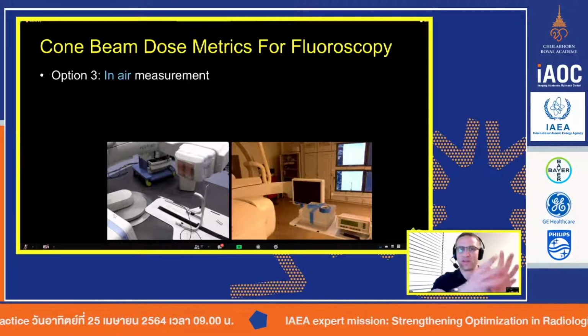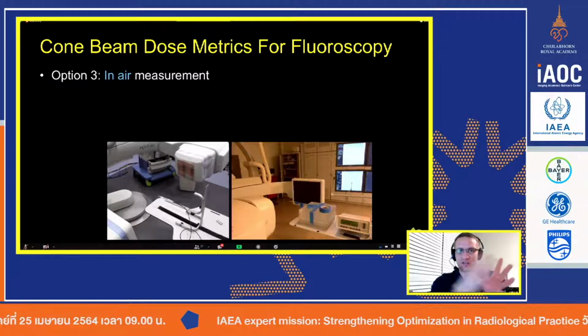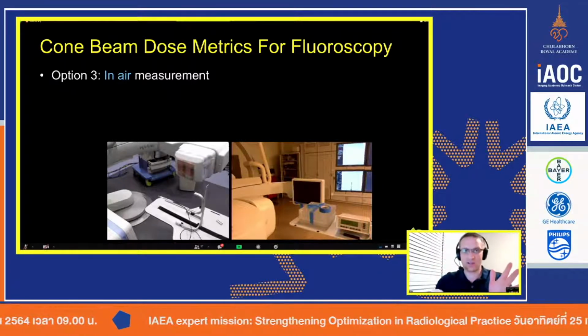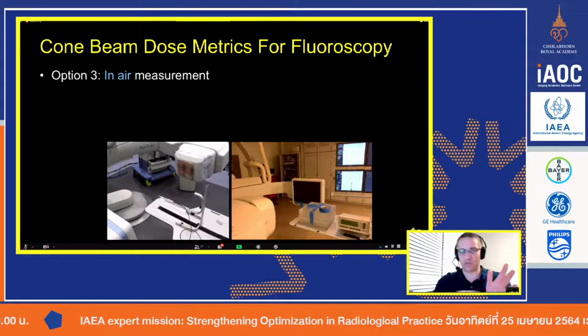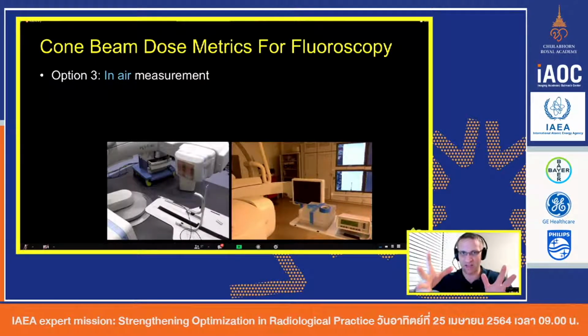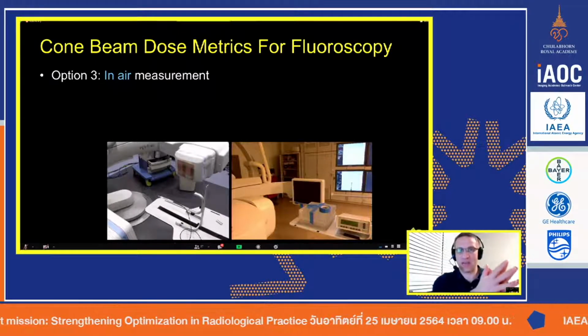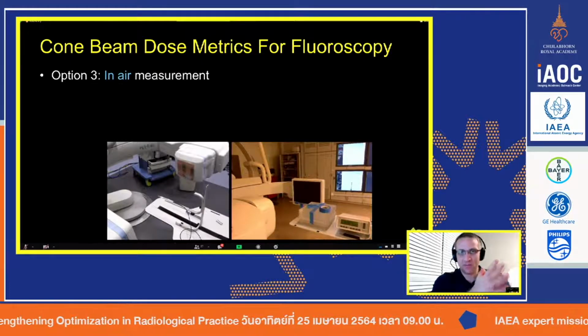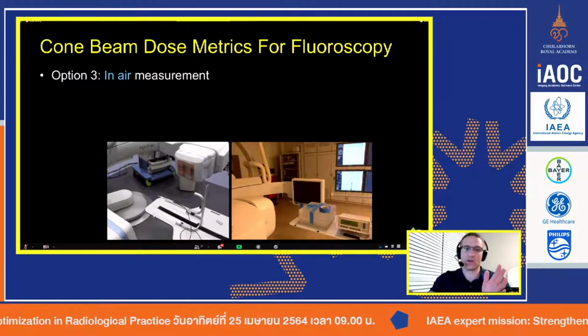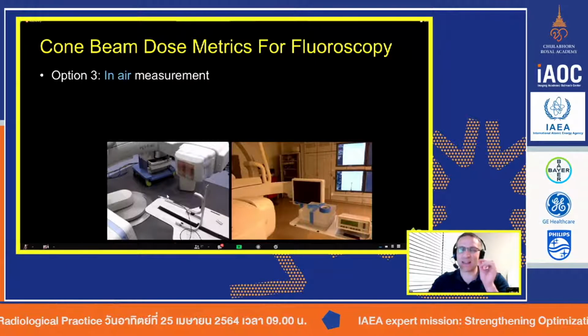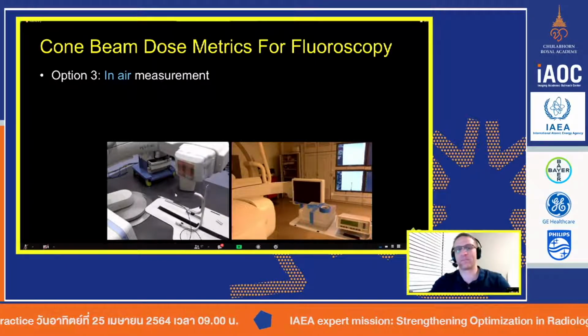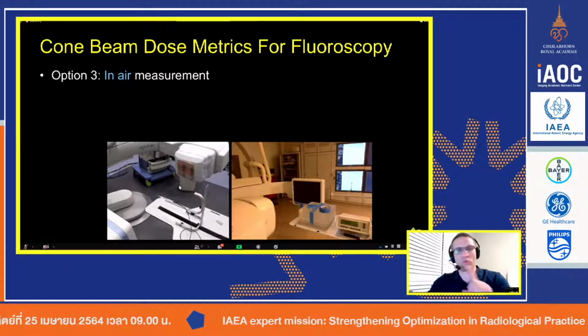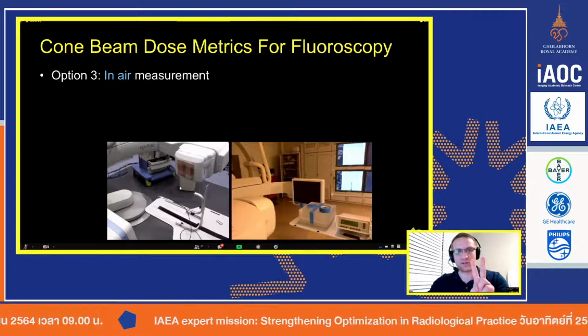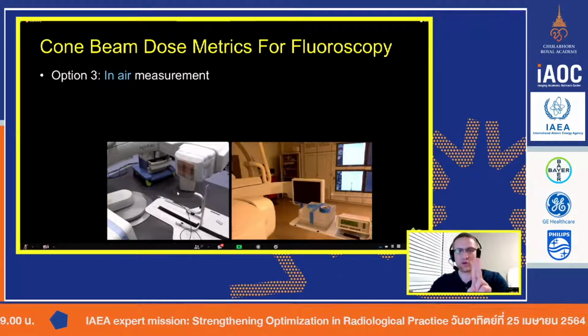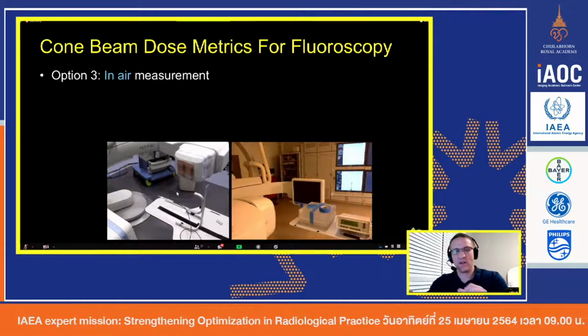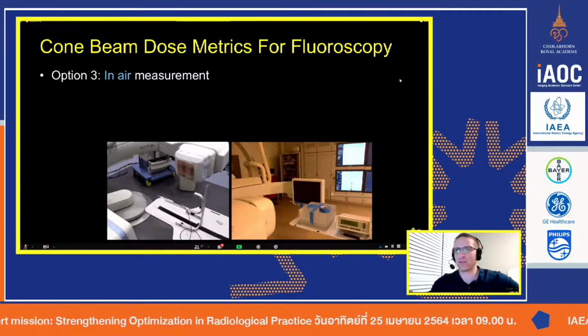Whereas if you put the filters on the detector side, well, the filters are still going to cause the system to change the automatic exposure rate controls. It's still going to make the system use the same output every time, but the dose that you measure on the ion chamber will be consistent. I personally believe it's more consistent that way. So use whichever probe you want. Make sure the field of view, if you use the 100 millimeter chamber, is smaller than the chamber. And then I personally put the filter on the detector.